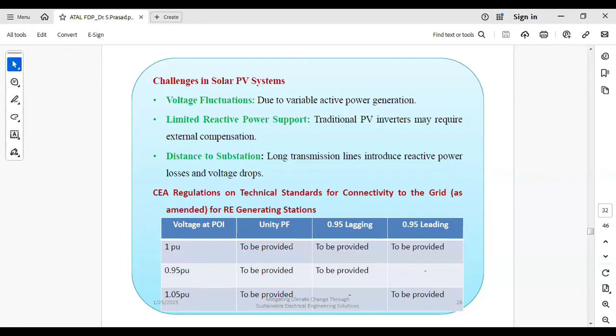So we have to follow the CEA regulations while conducting each test, and the standards we follow for each test. Sometimes you can also get reactive power support from the inverter end, because the inverter can also support reactive power to the grid. Though you should have a balance, a compromise solution between the rating of the capacitor banks or STATCOM or SVC and the inverter support you are getting. Inverter can also supply reactive power, but you have to control the power factor of all the inverters.